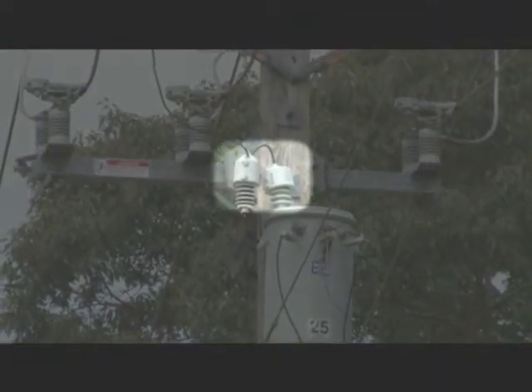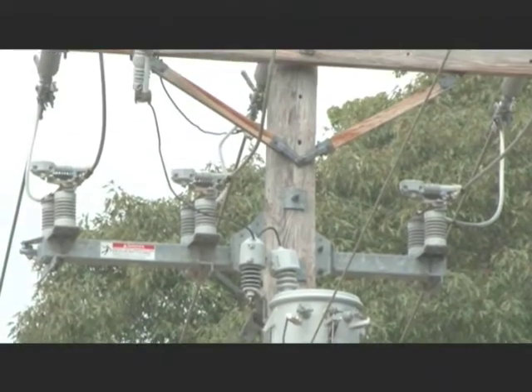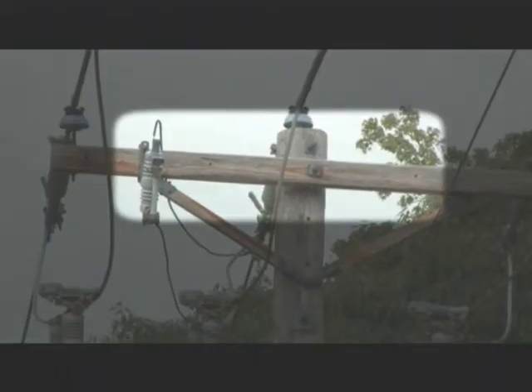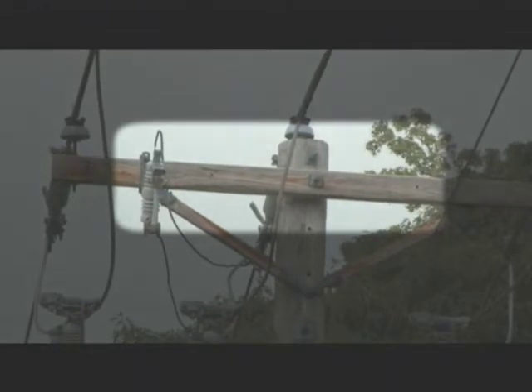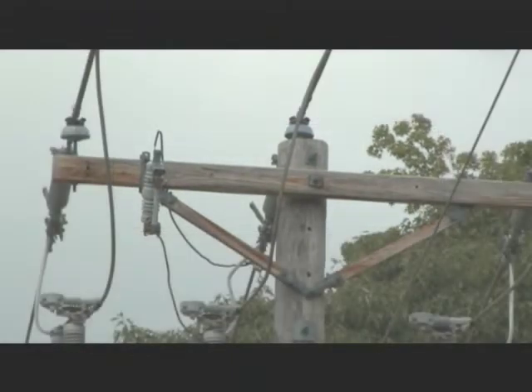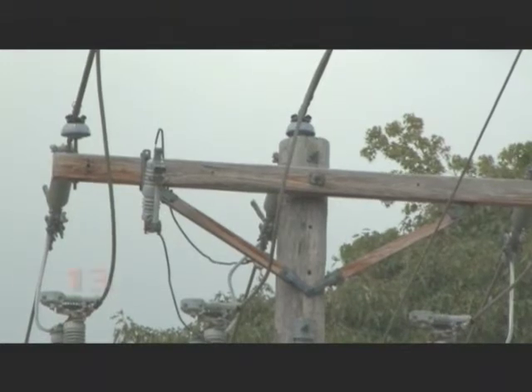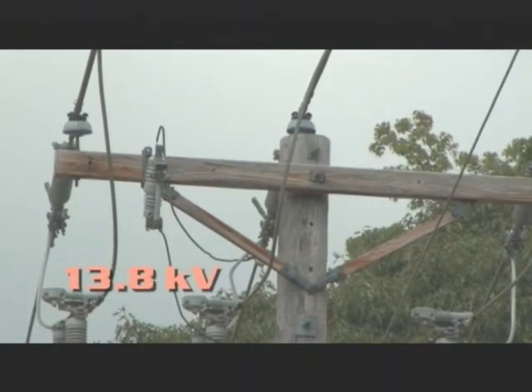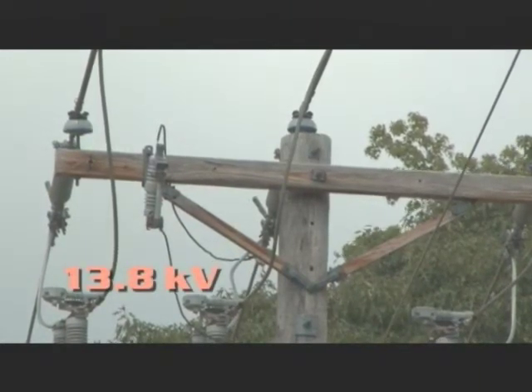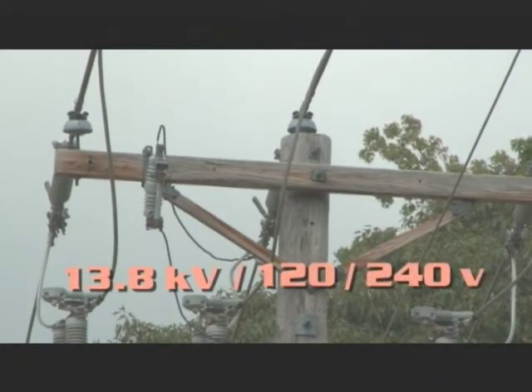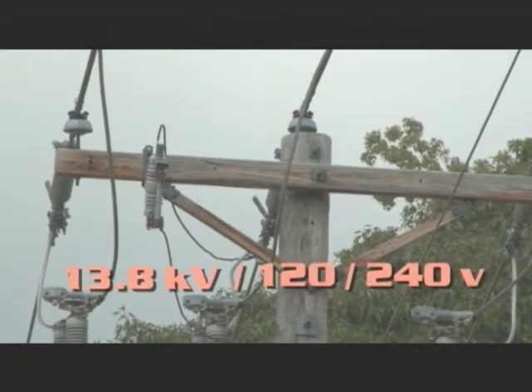On top of each transformer, there are one or more bushings. These bushings are connected to the high-voltage distribution conductors at the top of the pole. These high-voltage conductors are called primaries. They carry electricity from the substation at a voltage of about 13.8 kilovolts. Distribution transformers commonly reduce this voltage to 120 or 240 volts, which is a common voltage used by consumers.